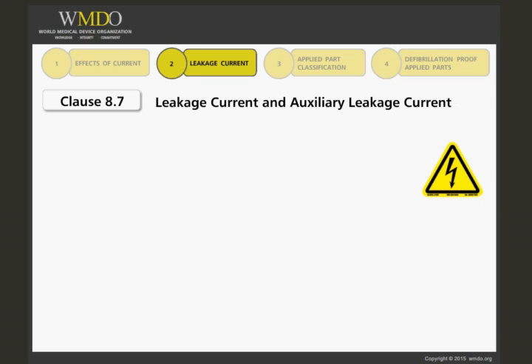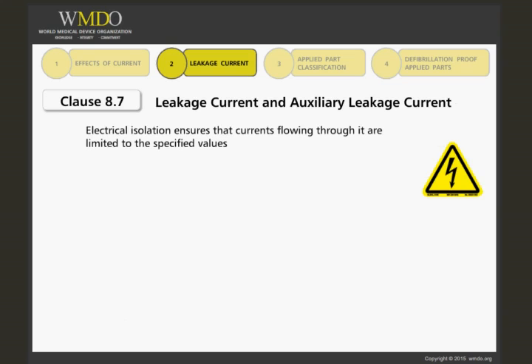Now we will cover leakage current and auxiliary leakage current. The standard states that electrical isolation providing protection against electric shock shall be of such quality that currents flowing through it are limited to the specified values. This means that measured values of leakage current and auxiliary current should not exceed the limits specified in the standard.